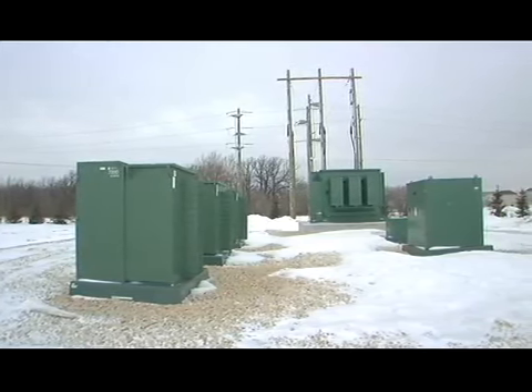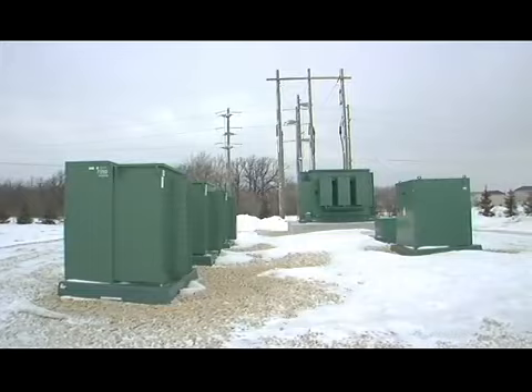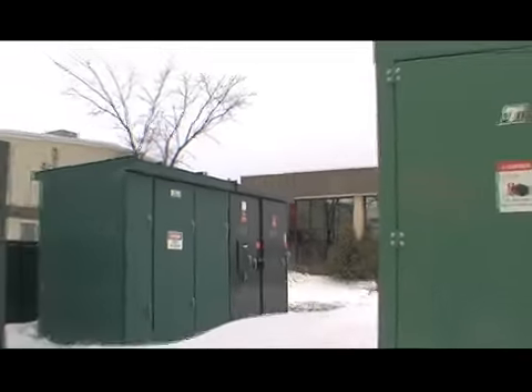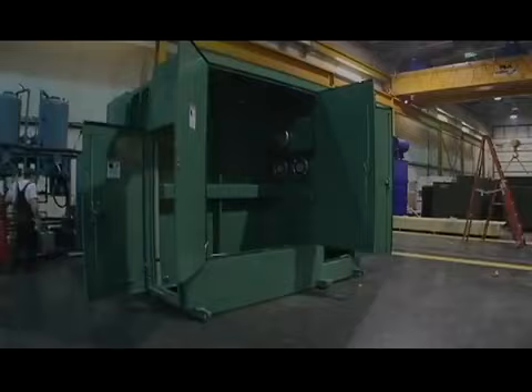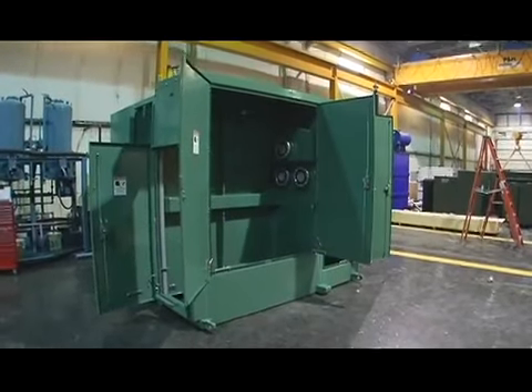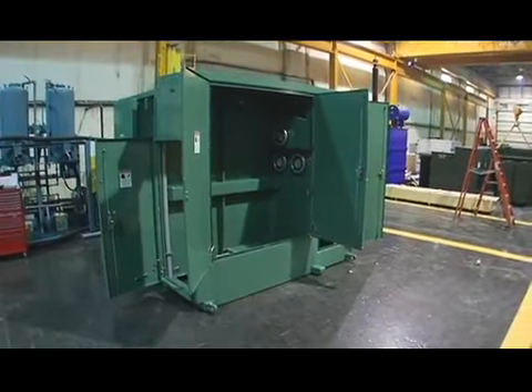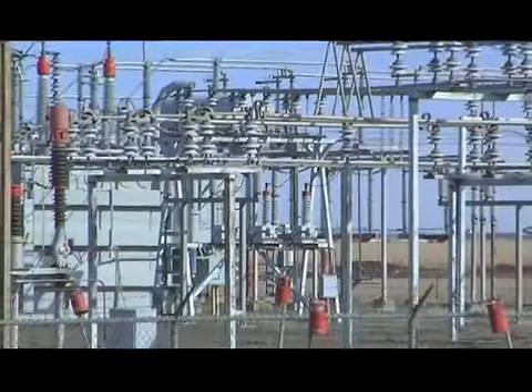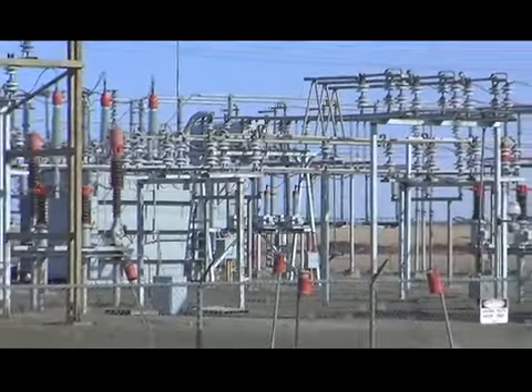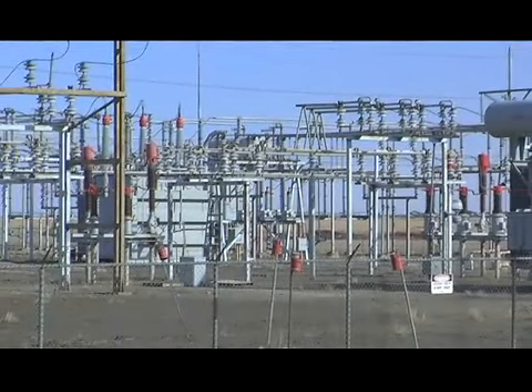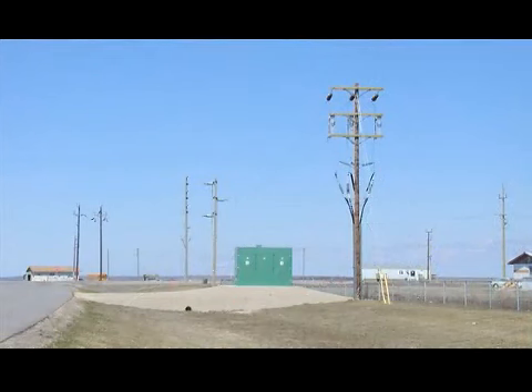The modular design allows for the addition of other necessary pad-mounted equipment to be a part of the distribution supply center. This modular design results in utilities being able to avoid the construction costs associated with larger stations, eliminating the need for building substation infrastructure and transformer capacity for potential future loads. Instead of building a large capacity station in one location that would have the capability of feeding the entire substation or subdivision, we'd be able to install these things as the load actually shows up.